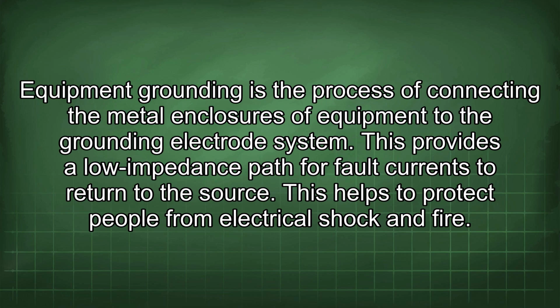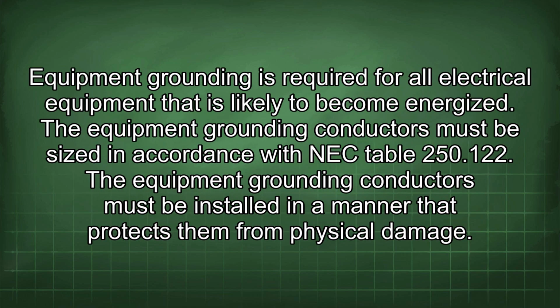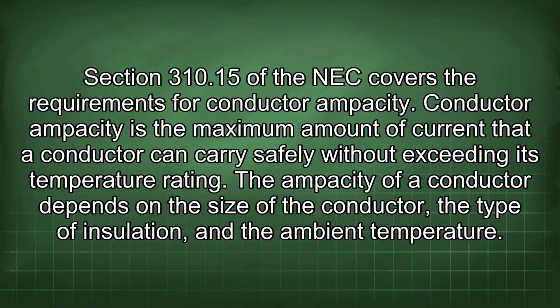This helps to protect people from electrical shock and fire. Equipment grounding is required for all electrical equipment that is likely to become energized. The equipment grounding conductors must be sized in accordance with NEC Table 250.122. The equipment grounding conductors must be installed in a manner that protects them from physical damage. Section 310.15 of the NEC covers the requirements for conductor ampacity.